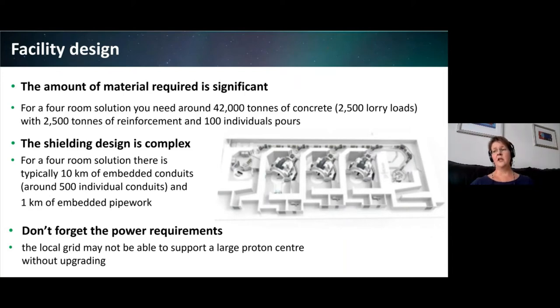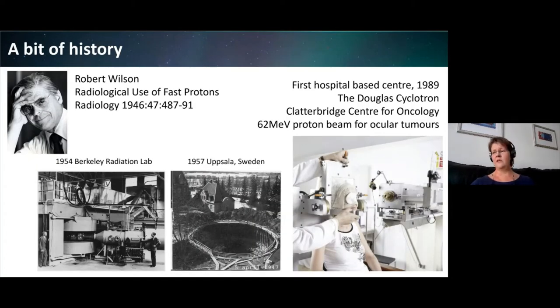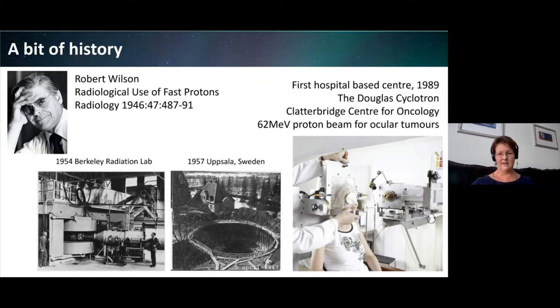For a large centre with a number of treatment rooms, the amount of shielding material required and the intricacy of the design — with penetrations for electrical and other services throughout the shielding — makes the design complex. The local power grids often don't have enough spare capacity to operate the facility, so you might need to factor in the cost, permissions, and siting of a new local substation. The first person to suggest protons could be an effective treatment method was Robert Wilson in 1946, widely recognised as the father of proton therapy. The first treatments were performed in particle accelerators built for physics research, notably at the Berkeley Radiation Laboratory in 1954 and Uppsala in Sweden in 1957. The wide use of protons was limited by the need to accurately determine the target tumour volume.